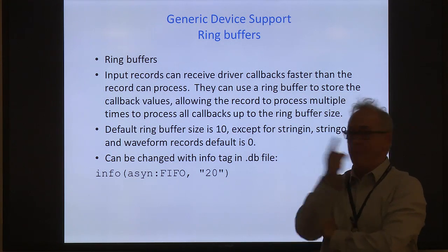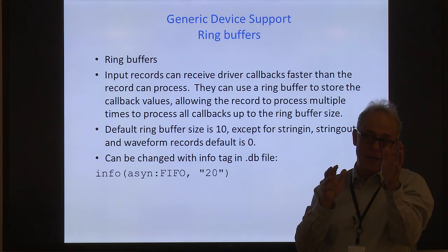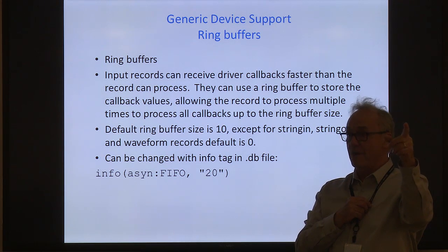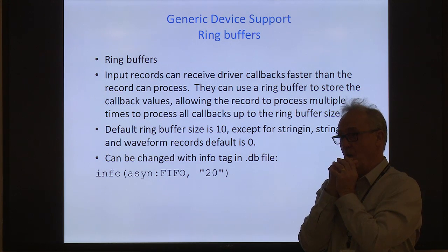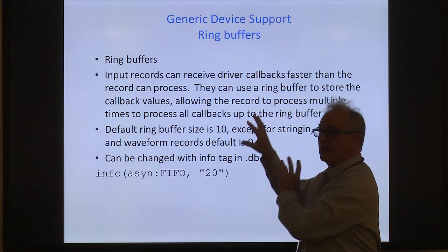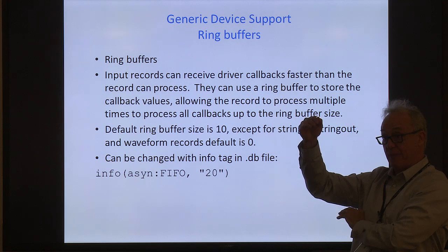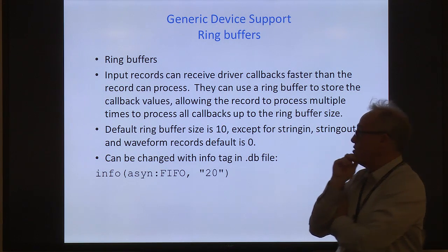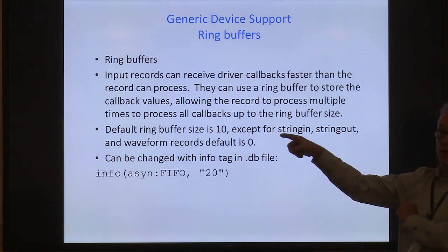The driver just does callbacks whenever it wants to do a callback. Device support decides whether to put those into a ring buffer, and if so, how big it is. Device support is at the level of asyn, so it is all in asyn. I'm talking about the standard asyn device support, the device support for all the records in EPICS base. The ring buffer is used by default on all records except string in, string out, and waveform.